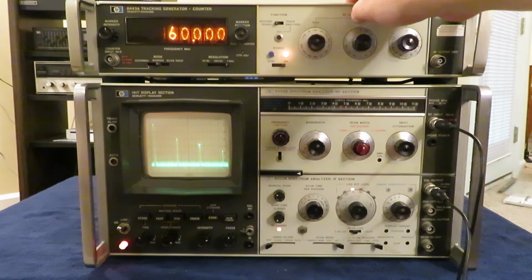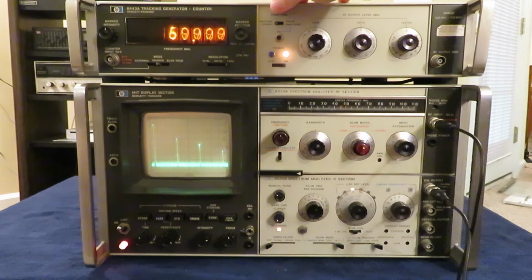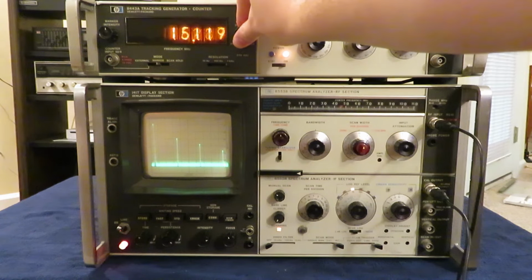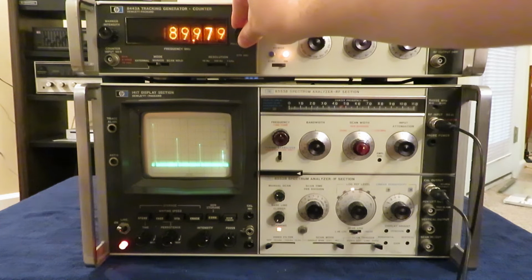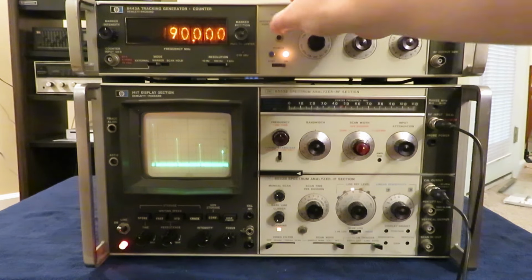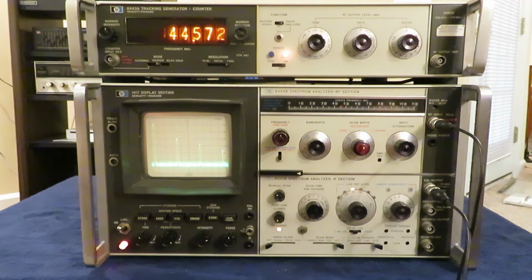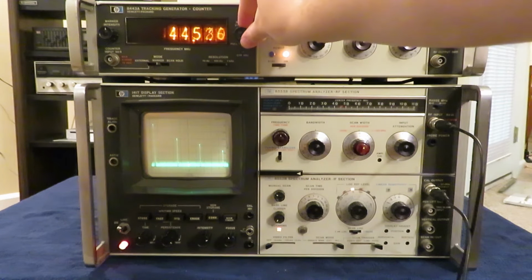The other mode that it has, so right now it's in restore signal, so that's what allows it to lock onto whatever peak the cursor is hovering over. Or you can set it to track analyzer, where it just becomes a general cursor that shows you what frequency you're at on the plot. And this will be useful also for the tracking generator later. I'll demonstrate how to use that. But this doesn't require a signal to lock onto. It just roughly tells you where on the sweep you are with that cursor.